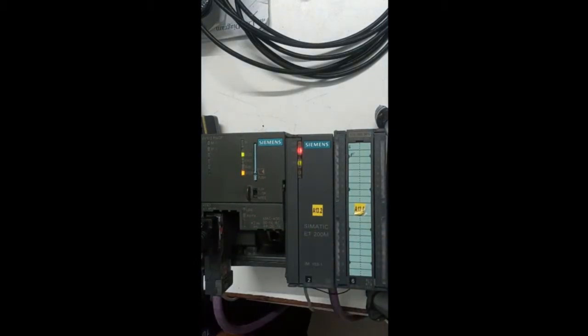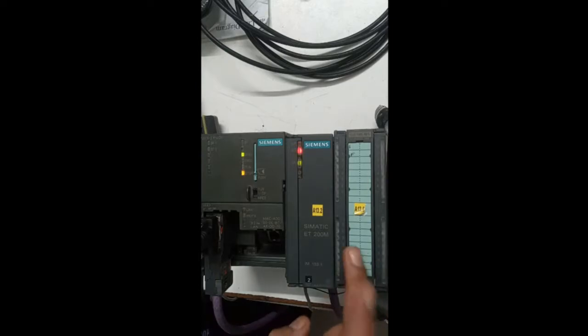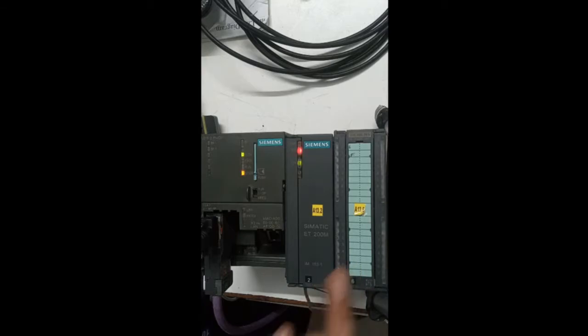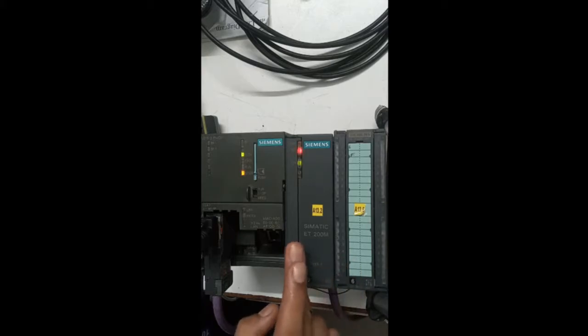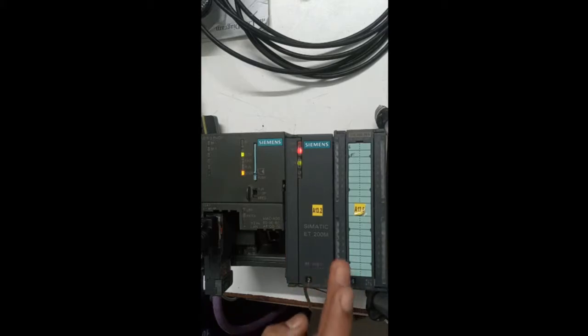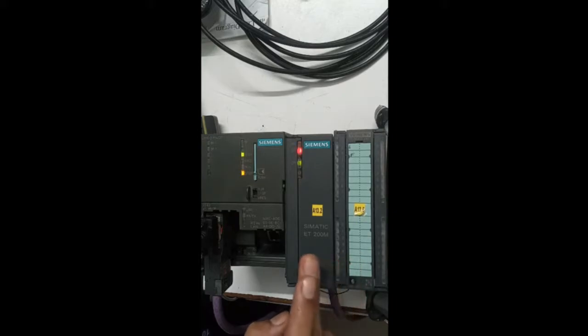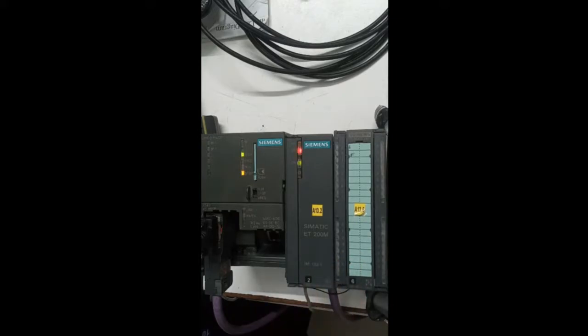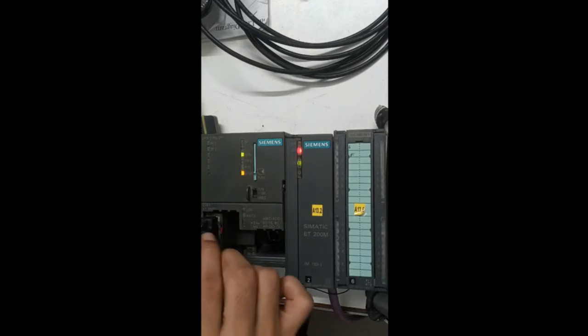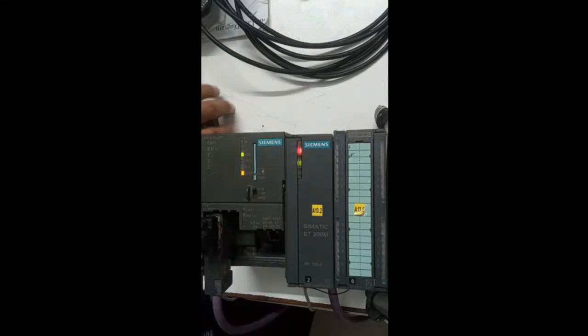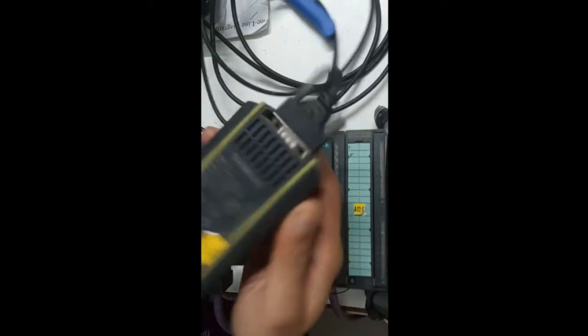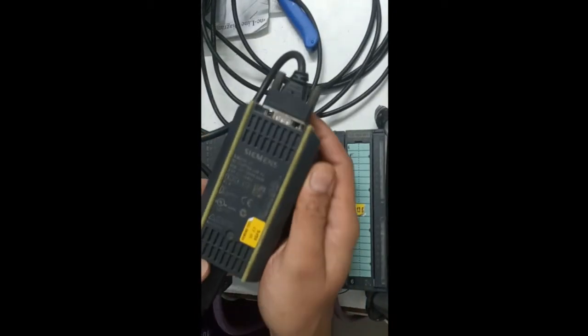It is necessary to connect at least one module, either digital input, digital output, or DI/DO module with the ET200M. If you do not connect any external module, it will give you an error while doing hardware configuration and downloading. I have connected the MPI cable with the Profibus.